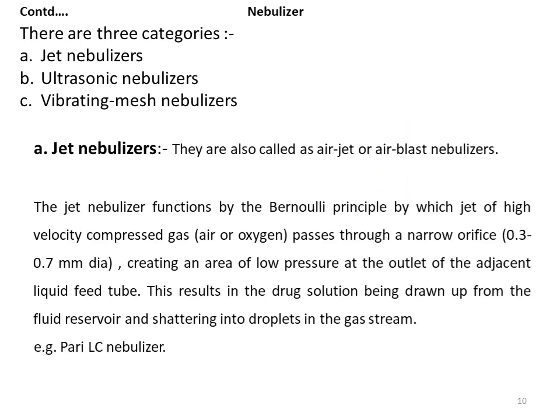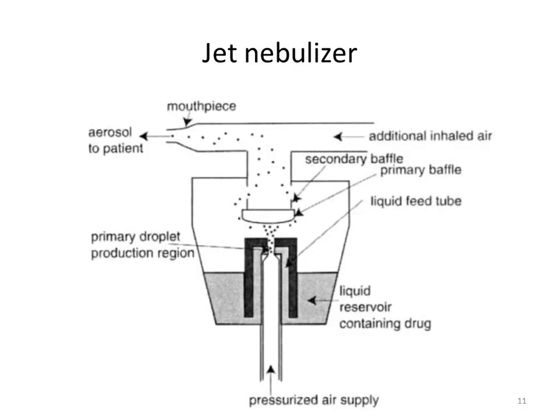There are three types of nebulizers: jet nebulizers, ultrasonic nebulizers, and vibrating mesh nebulizers. Jet nebulizers are also called air-jet or air-blast nebulizers. They function by Bernoulli's principle, by which a jet of high-velocity compressed gas — air or oxygen — is passed through a narrow orifice of 0.3 to 0.7 mm diameter, creating an area of low pressure at the outlet of the adjacent liquid feed tube. This causes the drug solution to be drawn up from the fluid reservoir and shattered into droplets in the gas stream. An example is the pari-LC nebulizer.